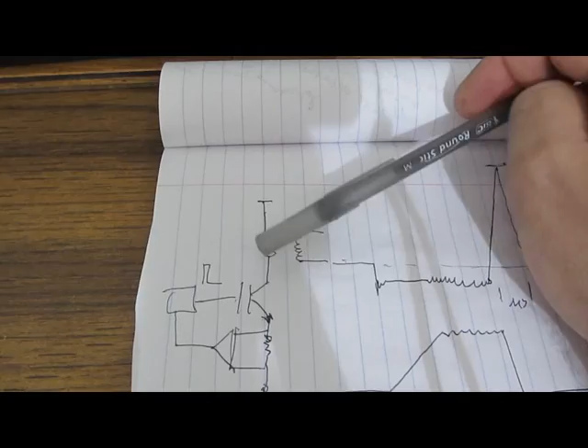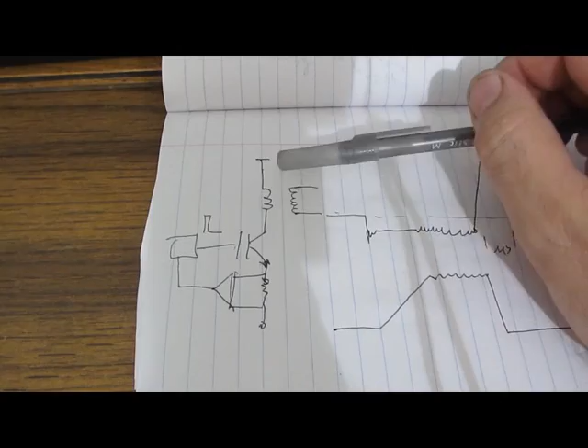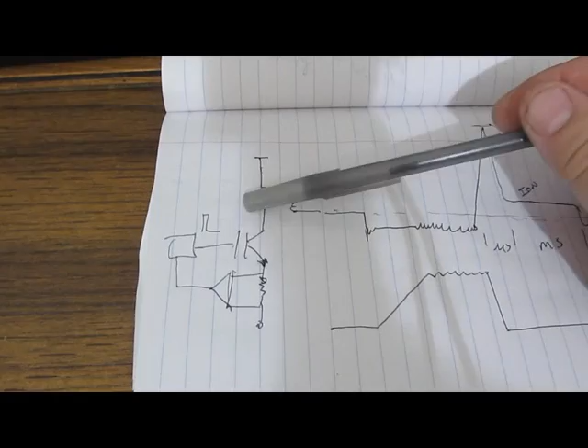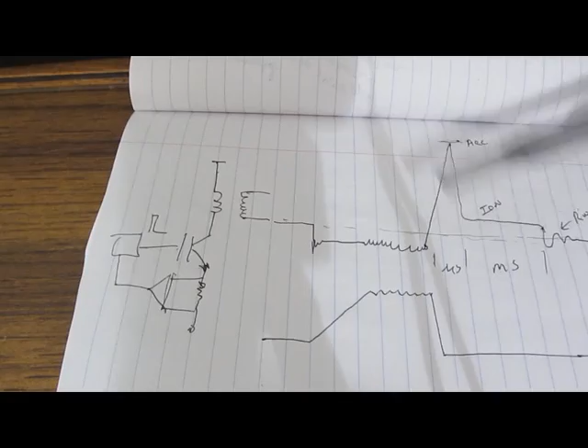I've had the probe attached to a neon sign transformer. Open circuit wise, I got about 20,000 volts out of it. I've also had it attached to my transient generator, which I used to test my multimeters. However, that transient generator right now will put out about 13,000 volts. It's a fairly high energy hit, but not enough to damage this probe. This probe is designed to handle well above what either of those two sources can put out.